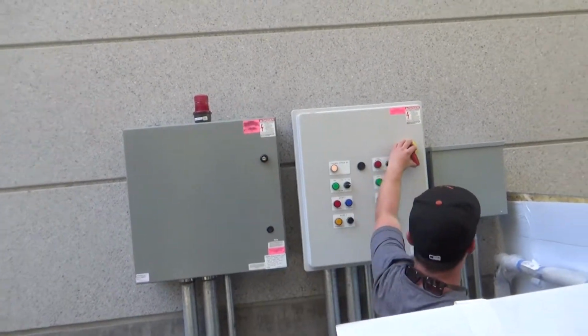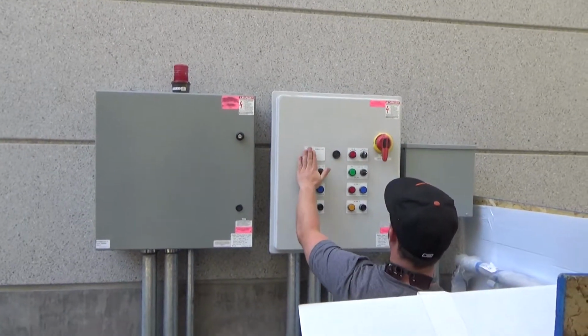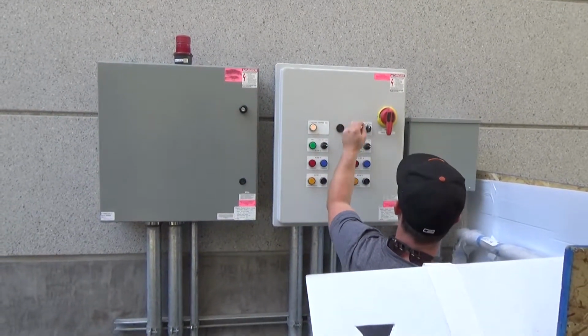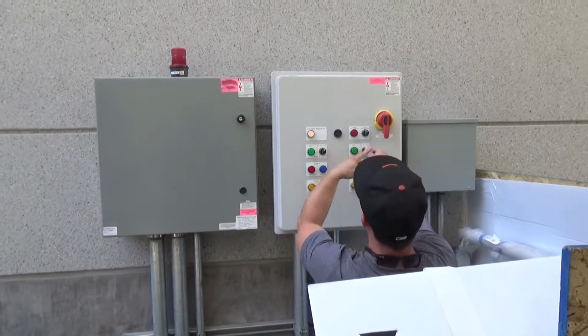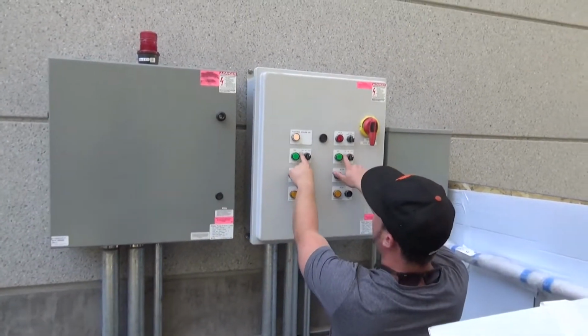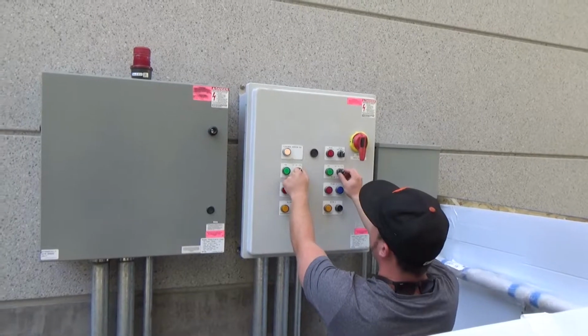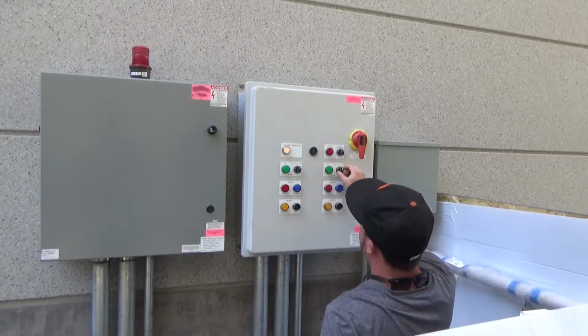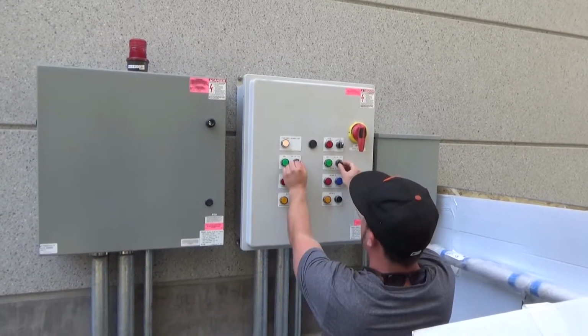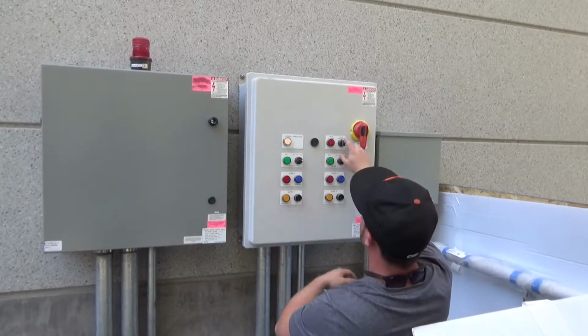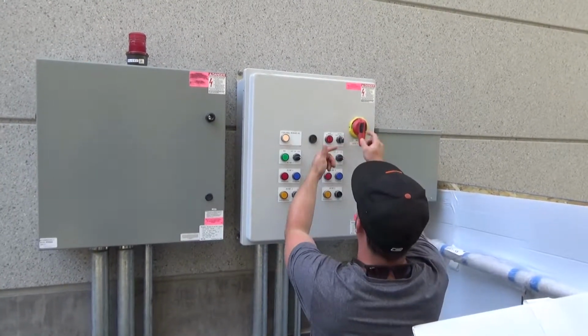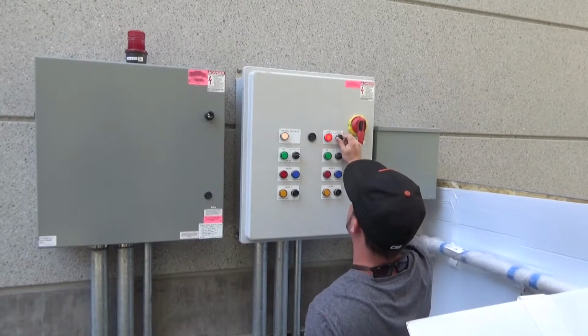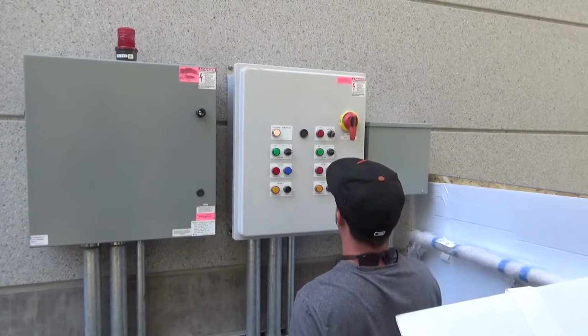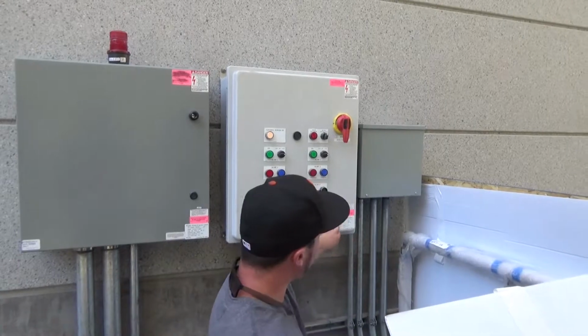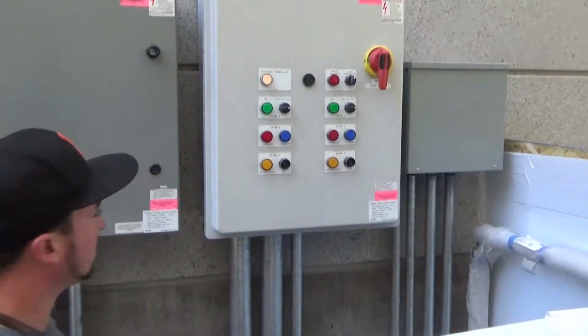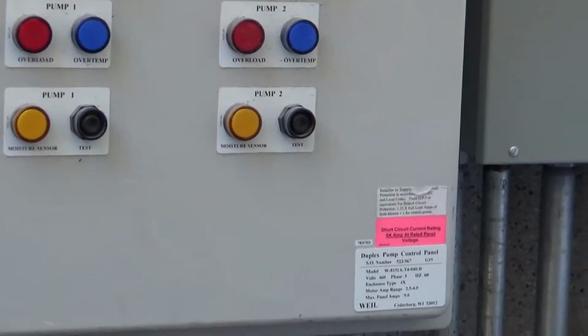Main disconnect panel right here, control light on, and every once in a while if you want to test, it's like the booster, you have hand off auto. They say test off auto, but if you want to test it, just flick it to the left, and if you want to turn both pumps off, have it up, or you can have it in auto. Say you have a high water alarm, if you want to silence it, you can just do that. All the information for the panels is right here. And let's see what else is there.